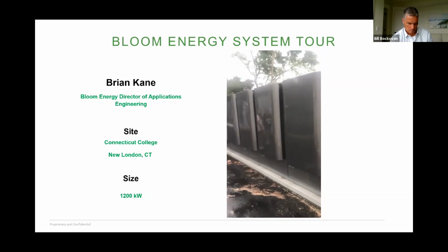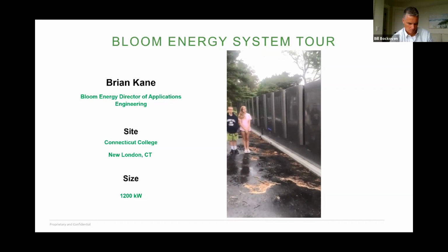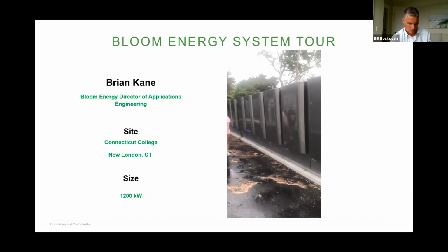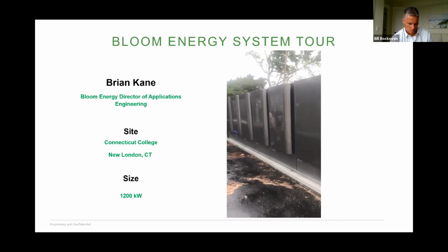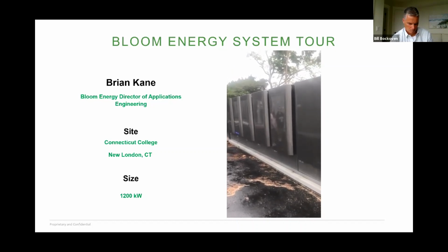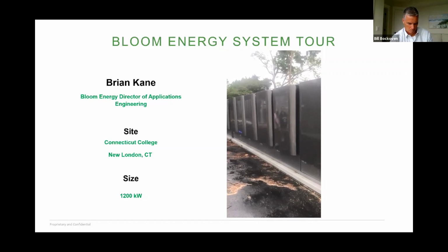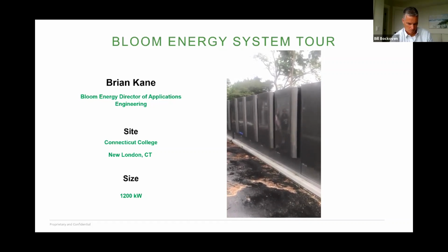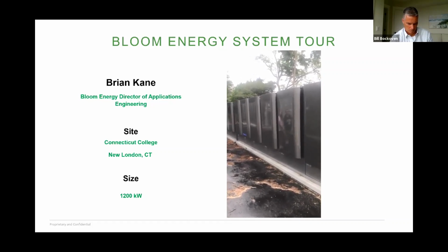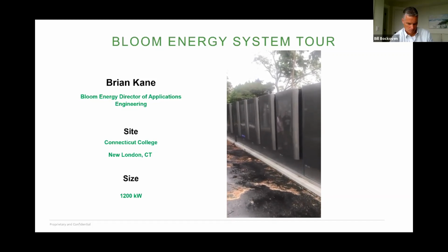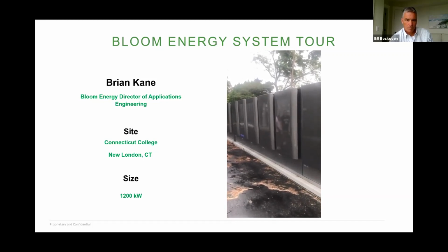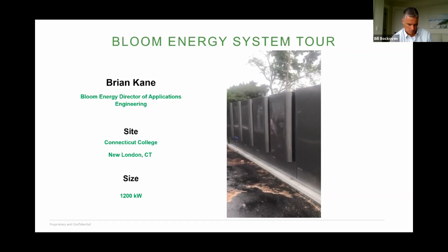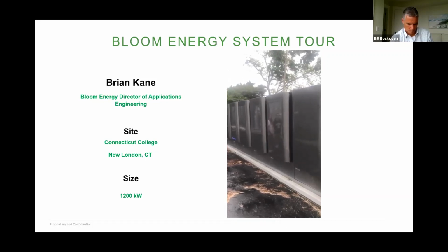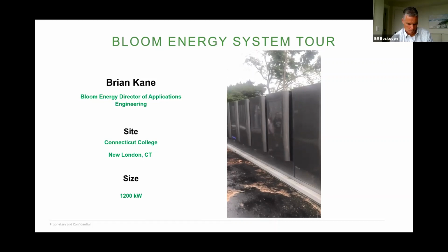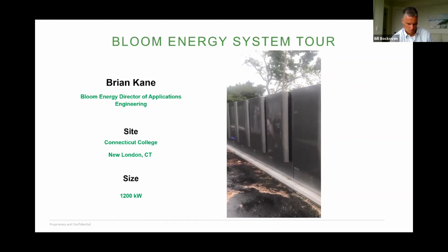Immediately to my daughter's left and coming back towards us are 5 power modules. Inside that power module is the core technology of the fuel cell, manufactured by Bloom Energy. It is a solid oxide technology that electrochemically converts natural gas into DC electricity at an efficiency well above 50%. It is the most electrically efficient power generator ever invented at this scale.